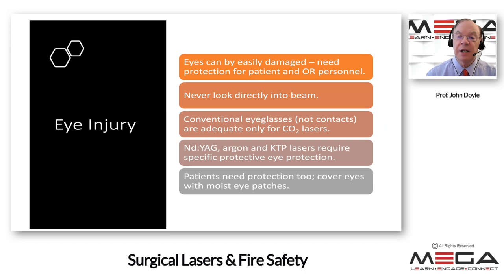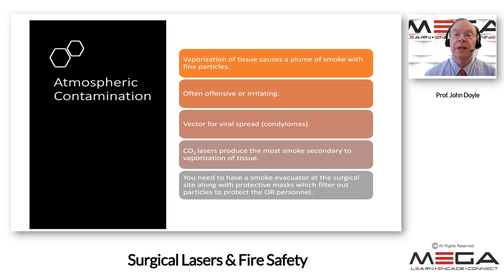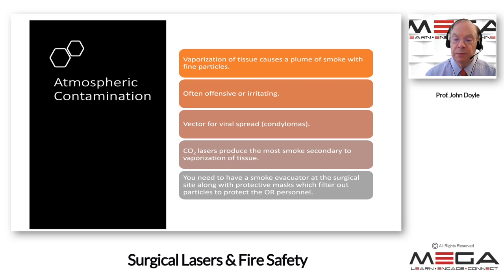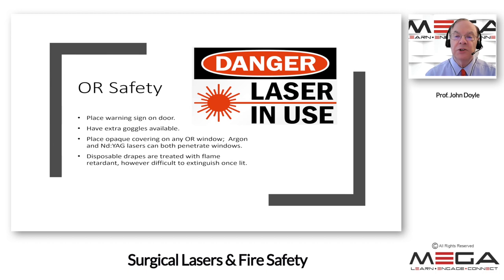Eye injury is a particular concern — never look directly into the beam. Conventional eyeglasses are adequate only for CO2 lasers; for argon, KTP, and neodymium YAG lasers, special eye protection is needed based on the wavelength of the light. For patients, cover the eyes with moist eye patches and tape them in place. Atmospheric contamination is another concern: vaporization of tissue causes a plume of smoke with fine particles that can be offensive, irritating, and potentially a vector for viral spread such as condylomas. CO2 lasers produce the most smoke; you need a smoke evacuator at the surgical site and protective masks filtering out particles.